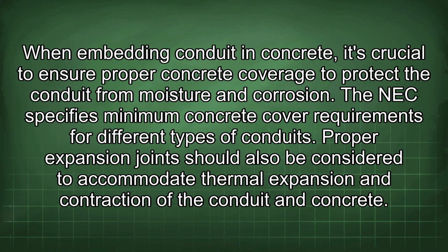When embedding conduit in concrete, it's crucial to ensure proper concrete coverage to protect the conduit from moisture and corrosion. The NEC specifies minimum concrete cover requirements for different types of conduits. Proper expansion joints should also be considered to accommodate thermal expansion and contraction of the conduit and concrete.